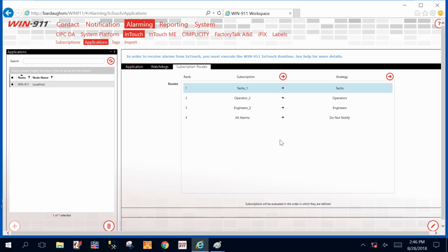So for our example, let's say we have the safety alarm goes off, the palletizer alarms go off for the light curtain. As the alarm comes in, it'll check against the Techs strategy, the Techs filter. Does this have the drive fault in it? No, so it's going to go down here. Does this have a group for safety? Yes, it does. So let's start our operators call out. Our operator strategy, which points to that call out list of people.